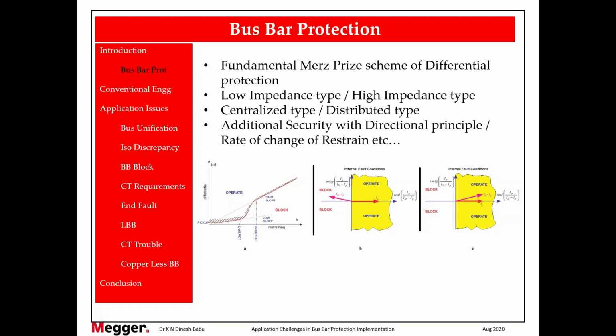So this is about the directional principle. And another concept is rate of change of restraint. Whenever a fault occurs, your differential current as well as restraint current both should increase simultaneously. If your differential current alone is increasing and restraint current is not increasing, it is not a fault.